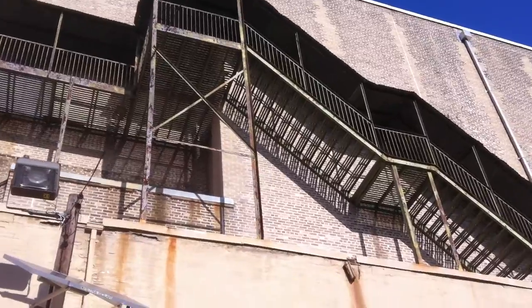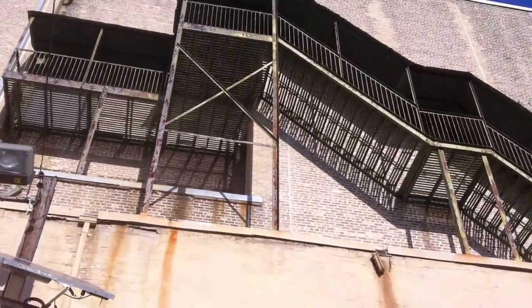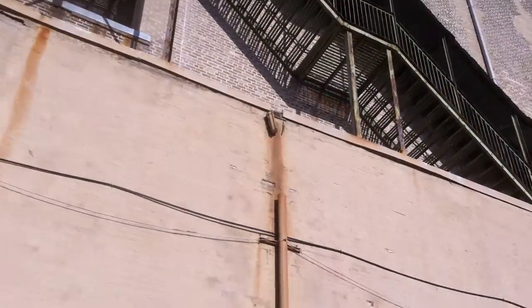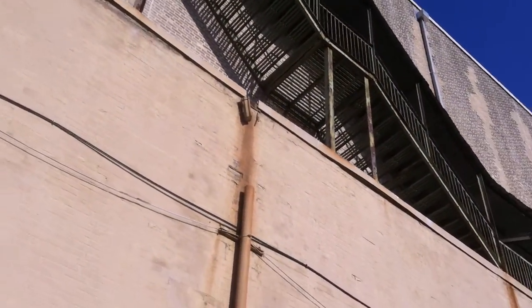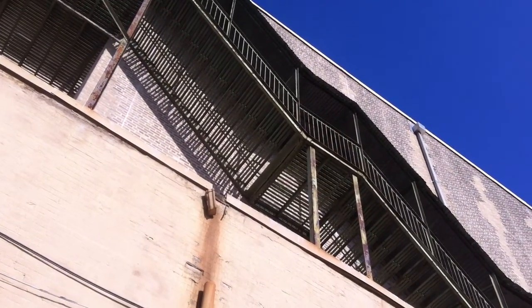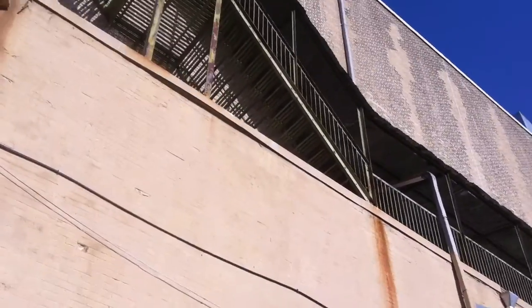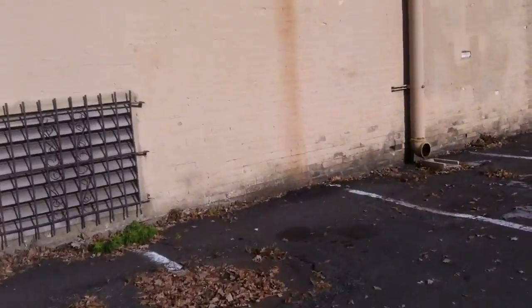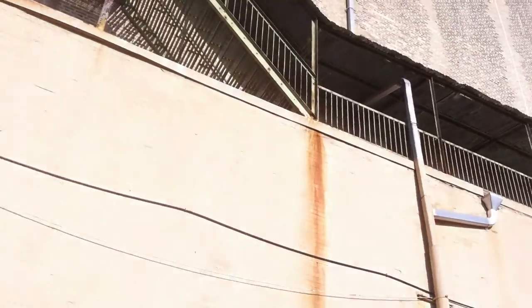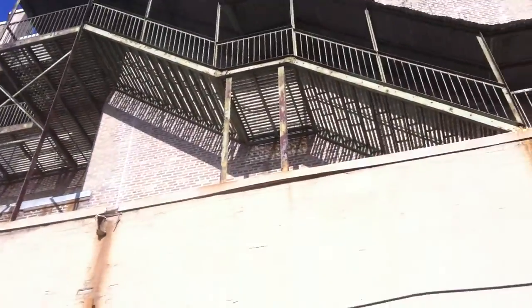Can you see any rusty tears? Can you see any rusty tears on the treads? Every piece of it. Now see this huge angle right here. Can you see huge amounts of rust in that angle right there? Yes. Is that normal? No. All right, let's continue walking. These rusty tears coming down the whole wall. Is that an indication that something's rusting? Everything inside. Yes. That it's gotten into the building and it's rusting? So let's keep walking. You don't see any evidence of maintenance here. It's all original hardware still, right?